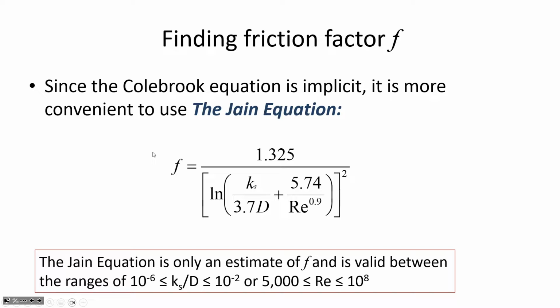But cast iron with water flowing through it at a high velocity, you'll have a different f value, because those would be two separate Reynolds numbers. Even though the pipe diameter is the same and the pipe material is the same, different flow velocities will give you different f values. And that's actually part of why we go to the trouble of using the Darcy-Weisbach equation: it's the most accurate way to estimate pipe friction. It's more accurate than other techniques I'll show you later on.